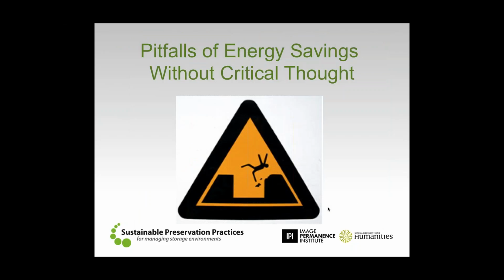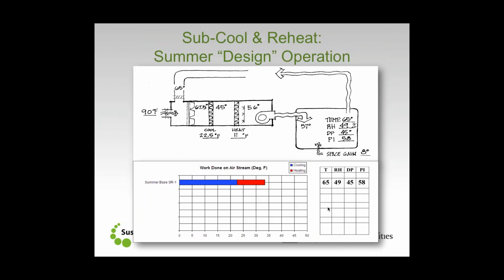Now, I wanted to put a picture of the video game Pitfall up there because that's what that word always brings to mind for anybody who is a child of the 80s and used to play the old Atari games. But what happens oftentimes when we have the best intentions and we're going in and thinking, you know what, I'm going to save some energy, or worst case scenario, and this is not to pick on administration, but oftentimes administrations will put down that blanket mandate of, you know what, we need to save energy, we're using too much energy on cooling. So we're putting across a blanket statement that instead of cooling to 72 degrees in a space, we're only going to cool to 75 degrees in a particular space. We're going to change that set point, increase the space temperature, and we're going to save energy.